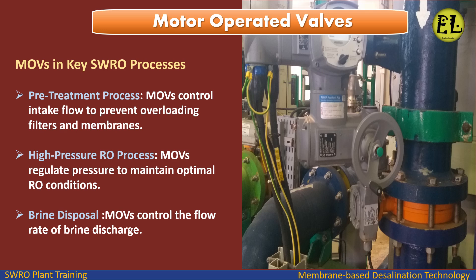MOVs play key roles in SWRO processes. In pre-treatment, MOVs control intake flow to prevent overloading filters and membranes. In the high-pressure RO process, MOVs regulate pressure to maintain optimal RO conditions. For brine disposal, MOVs control the flow rate of brine discharge.